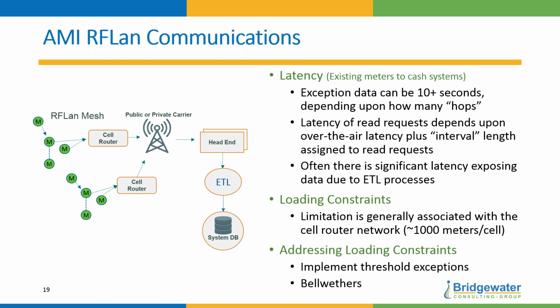Loading constraints, not too bad because it's dependent upon the cell router, but you can't ask for the data consistently. To address loading constraints, you can implement threshold exceptions that we talked about, or bellwethers. Bellwethers are meters that represent an area where you can read them every couple of minutes, and it gives you a handle on what's going on in that particular community. So you don't have to read all meters.